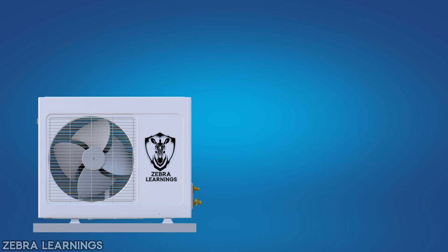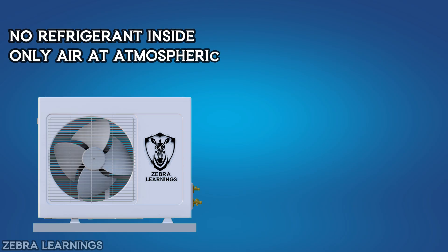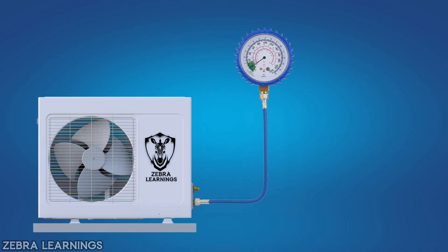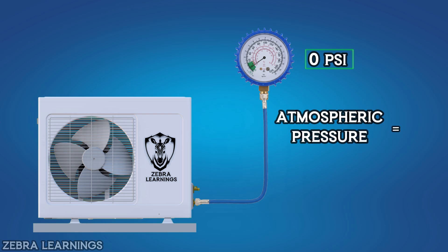Let's take an outdoor AC unit as an example. There's no refrigerant inside, only air at normal atmospheric pressure, which is 14.7 PSI absolute. Now if we check the pressure using a manifold gauge, it'll still show 0 PSI. Even though the actual pressure inside the unit is 14.7 PSI, the gauge reads 0, because it treats atmospheric pressure as 0 reference. To understand this better, let's see a few more readings.